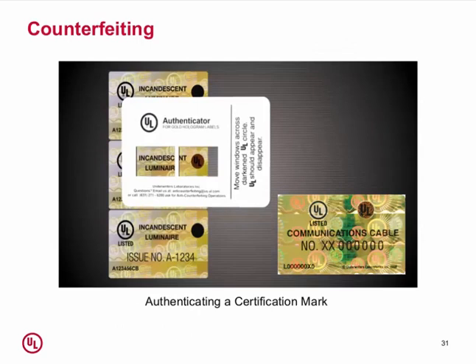At UL, in categories such as communications cable, we use holographic marks. Within the holographic mark, there are a bunch of different codes and things that can be looked for. One of the most obvious is what we call an authentication. We have these little tabs that we call authenticators. If you look at the label above the authenticator, you'll see it looks like a black dot. That's part of the holographic label. When I put the authenticator over it, you'd see the UL come out from that black dot. Usually it's not a UL, it'll be some sort of code, a letter, a number. If you don't see that type of change using the authenticator, then that holographic label is probably counterfeited.